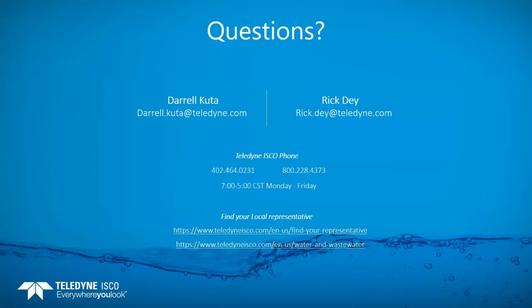So we can also set up so that we're looking for a text message. The modem can be set up to push data, let's say once a day, but I want you to check for a text message once an hour. That takes very little power, and it wakes up and says, oh, you're coming to the site. Okay, I'm going to open my Bluetooth up so that when the field crews get there, it doesn't take them a long time to connect up. So a lot of capabilities. We put a lot of effort into power and how we conserve power and make the batteries last as long as possible. So some good stuff with the Bluetooth.